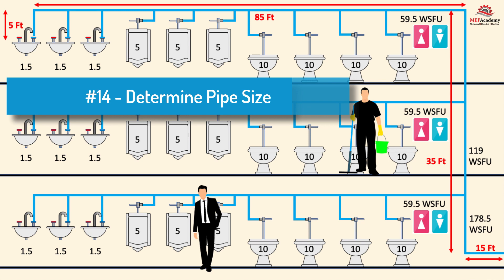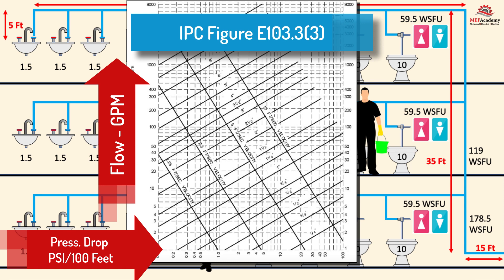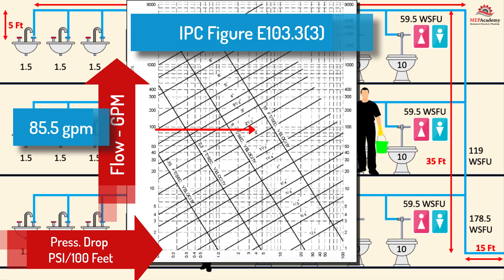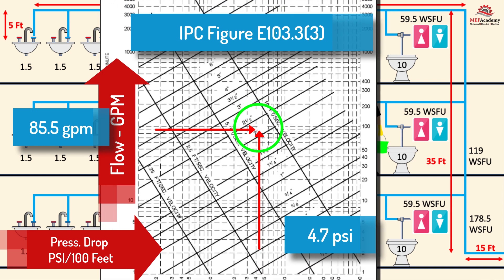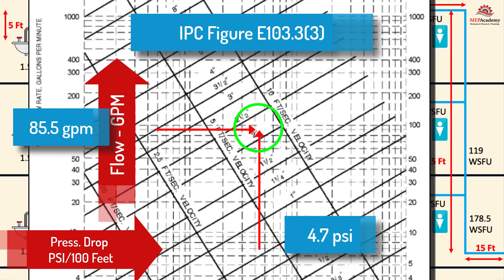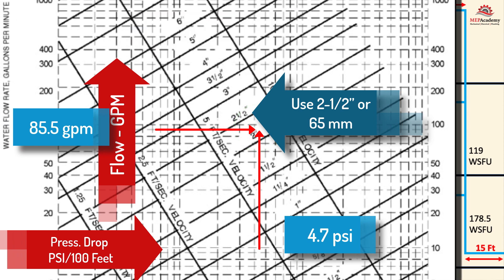Step 14: Determine Size of Water Service Pipe. Using IPC Figure E103.3(3), we enter the total flow of 85.5 GPM and the allowable pressure drop of 4.7 PSI per 100 feet; they intersect just above the 2-inch pipe line. To be safe, we'll specify a 2.5-inch or 65-millimeter pipe. If analysis revealed insufficient city pressure to overcome all losses and provide the minimum required pressure at the most remote fixture, a booster pump would be considered.